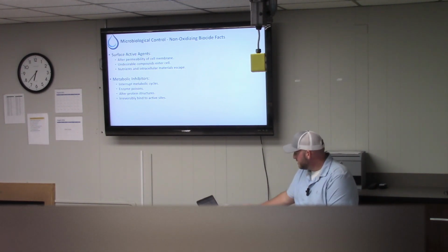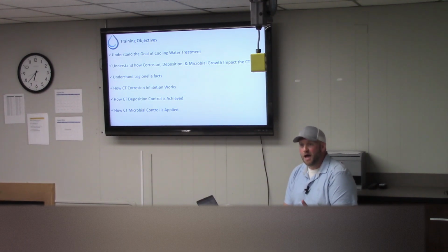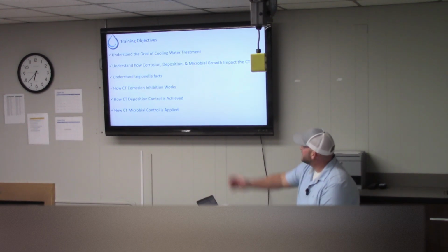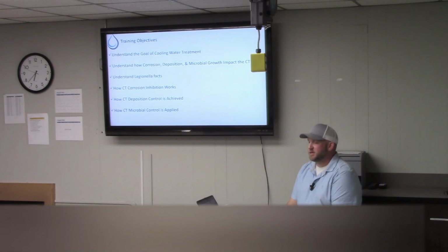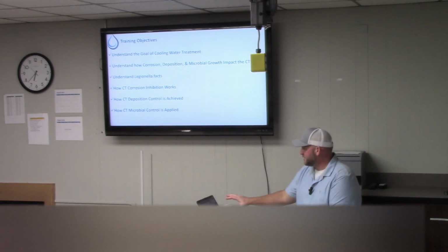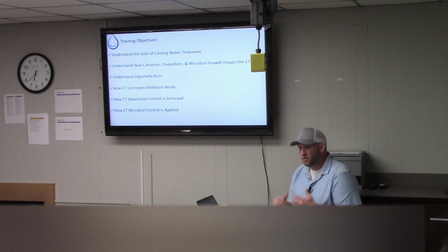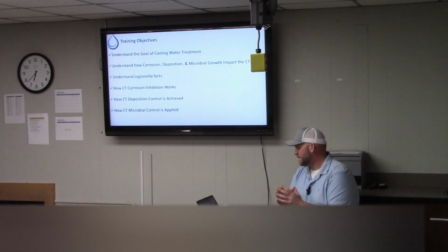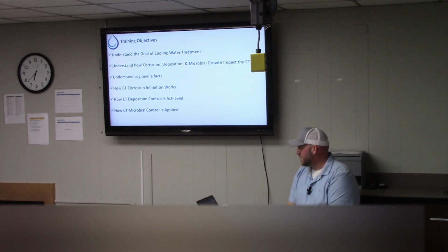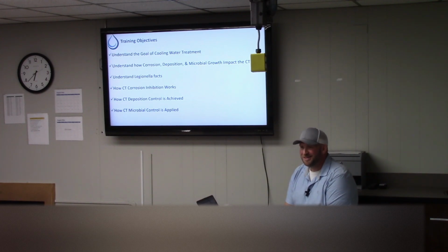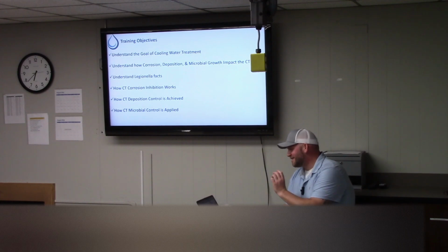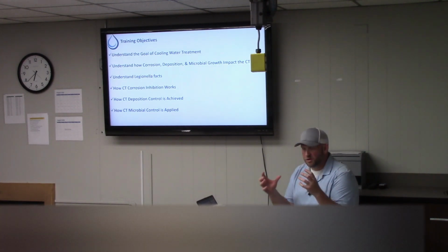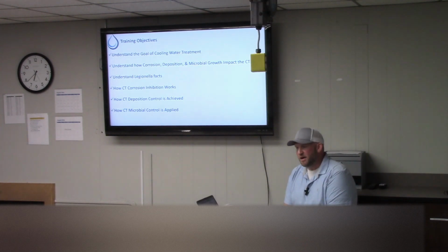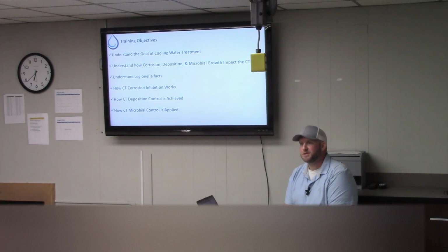We're at the end. As sad as that may be, it's still prudent to review the training objectives. We did a decent job understanding the goal of water treatment for cooling water, and how corrosion, deposition, and microbiological growth impact a cooling tower — remember that trinity. We understand Legionella is even worse, 3-to-1 not 2-to-1, and that the chemistry is more than snake oil. We now know how corrosion inhibition works, how deposition control works under the microscope, and why those biocides, no matter how bad they smell, are still worth putting into the system.